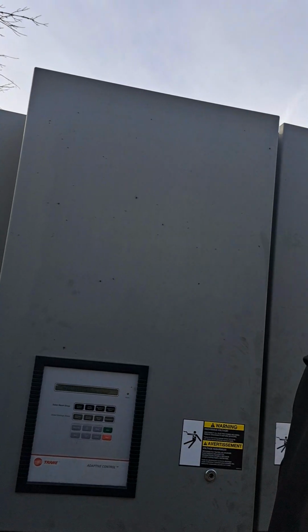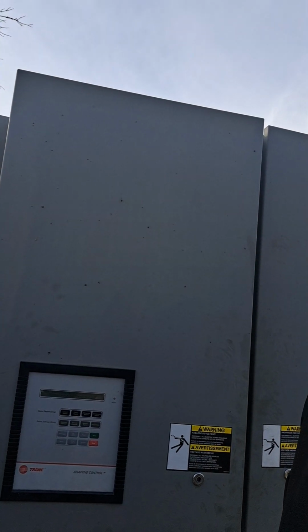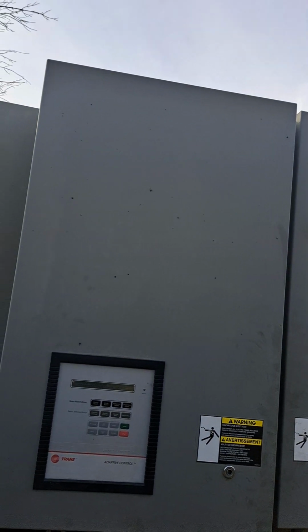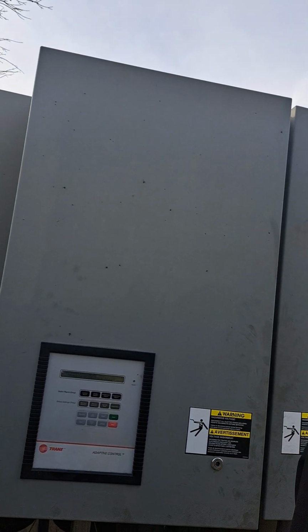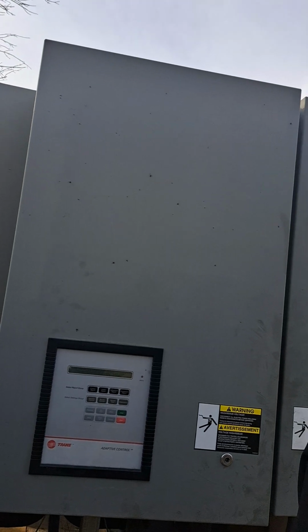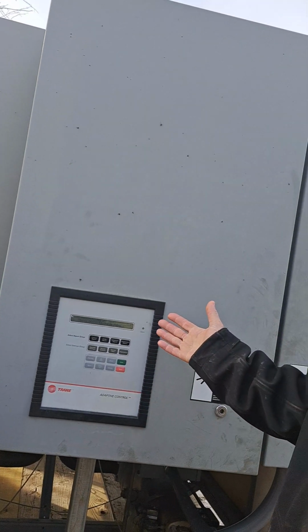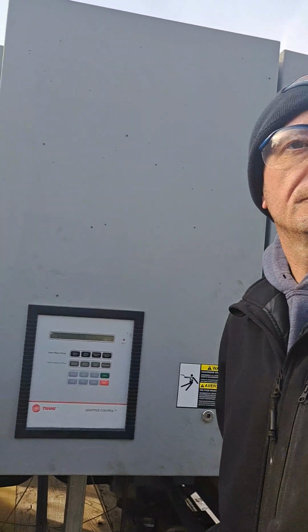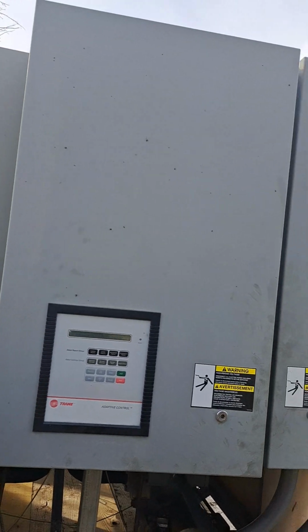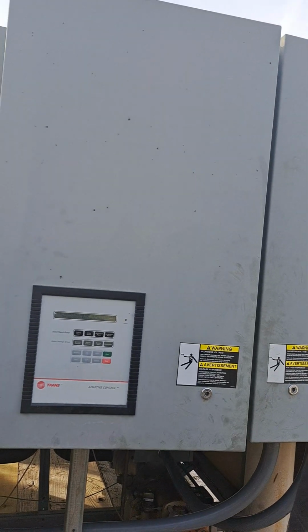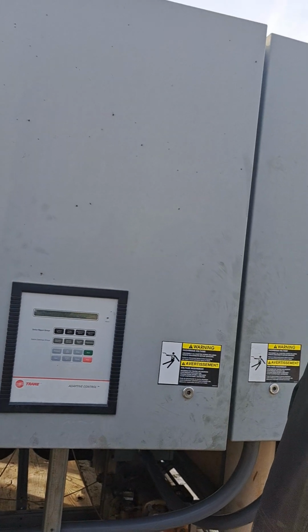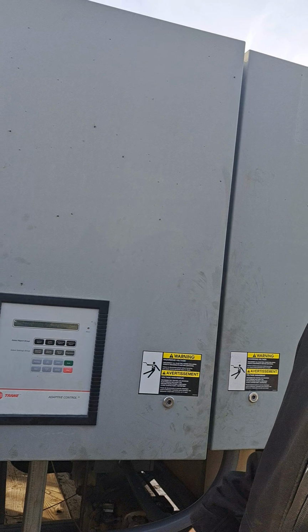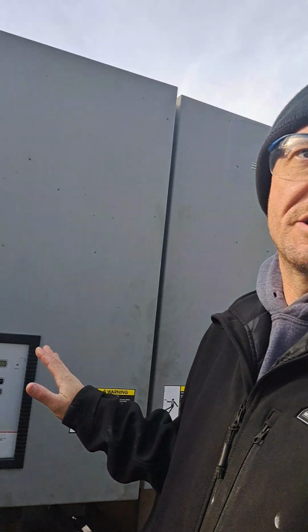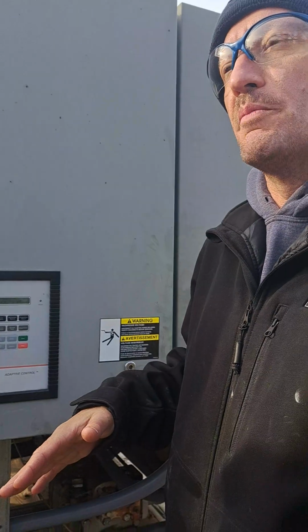Well, with the indoor rink that I was running, when we put the ice in, we're flooding and putting in stuff, we turn it down to I think 13 or 12 degrees, maybe 10. But then we normally keep it about 17, 18. Actually, 20, 21 is where you could do that here if you wanted to lower. And it would help a little bit with the speed of it, but other than that, if you wanted to turn it down to like 12, I don't think I'd go much lower than that because we're going to start locking out on safeties. Since this thing is running, I'm going to leave all the safeties where I set them. If I come in today and it was locked out on something, then I'd probably lower them a little bit more.